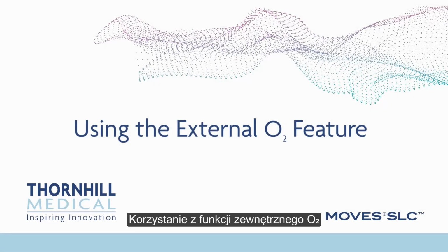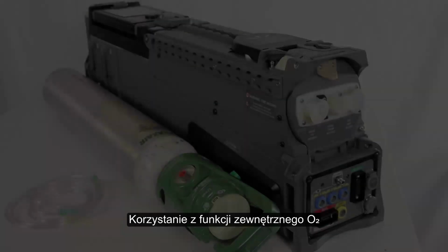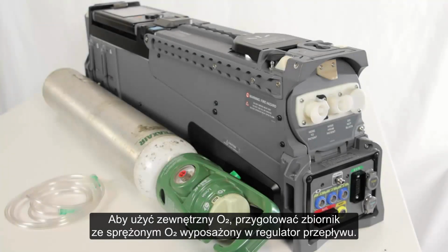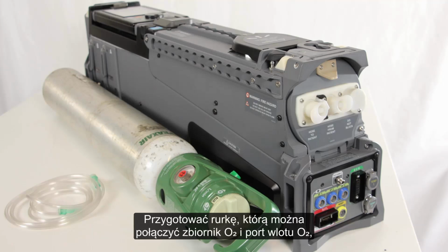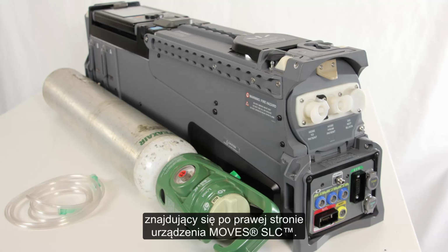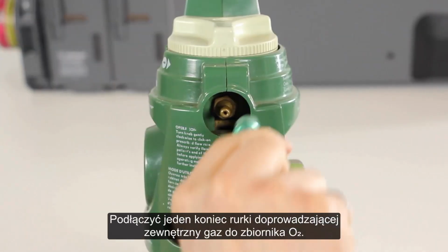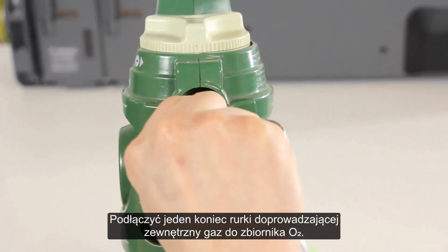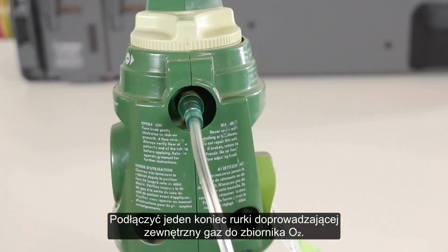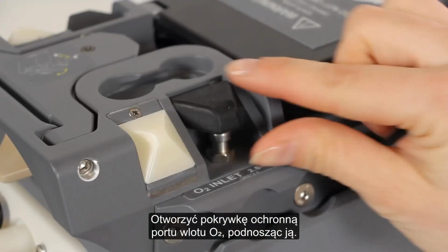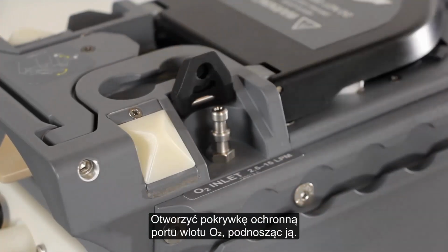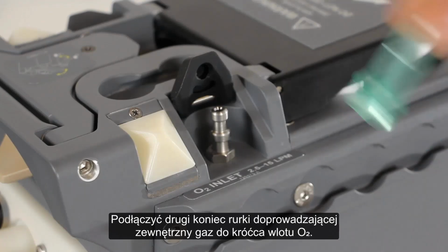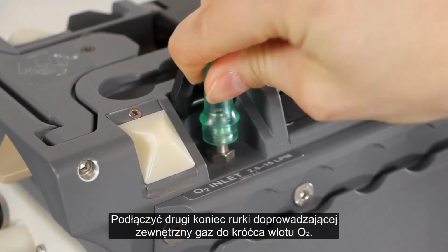Using the external O2 feature. To use the external O2 feature, prepare a compressed O2 tank fitted with the flow controller. Prepare a line of tubing that can be run from the O2 tank to the O2 inlet port on the right side of the Moves SLC unit. Connect one end of the external gas supply tubing to the O2 tank. Open the protective cover of the O2 inlet port by lifting it. Attach the other end of the external gas supply tube to the O2 inlet nipple.